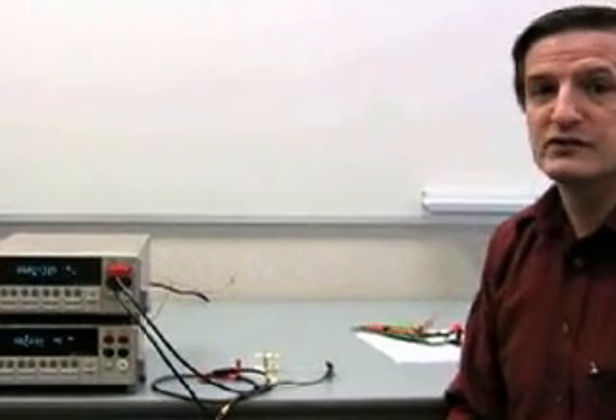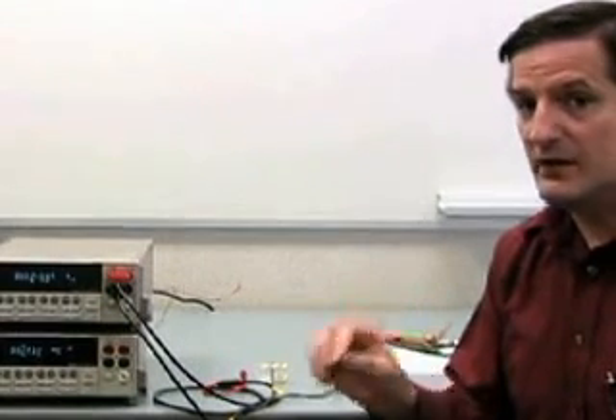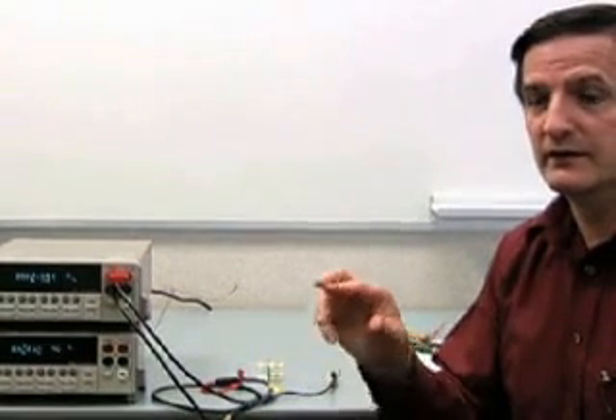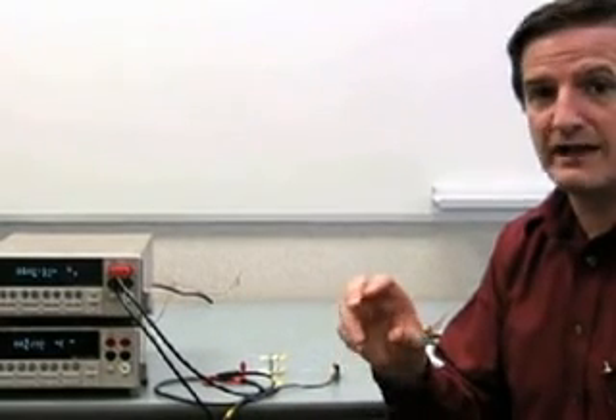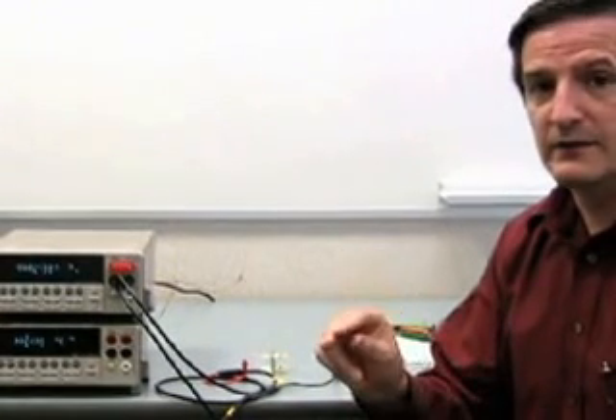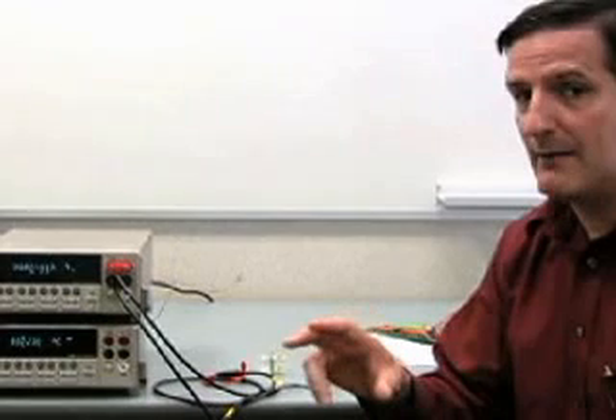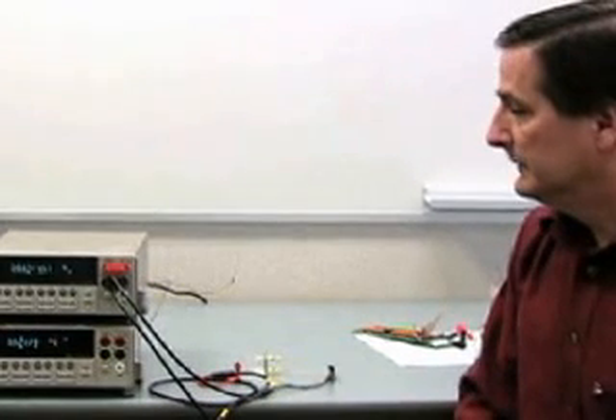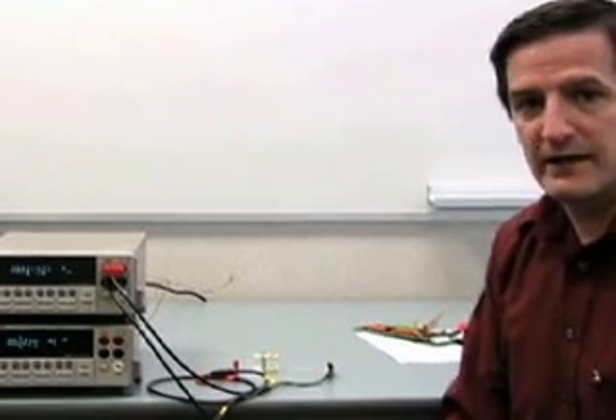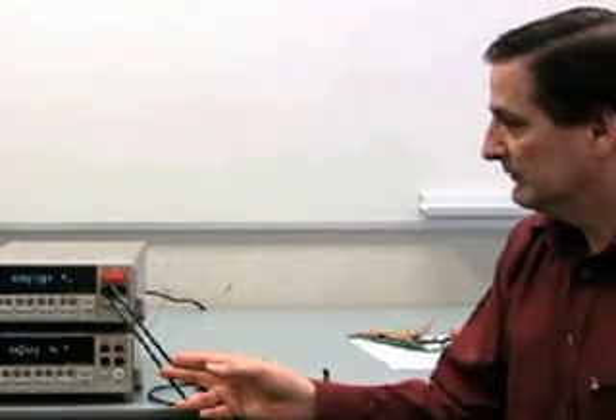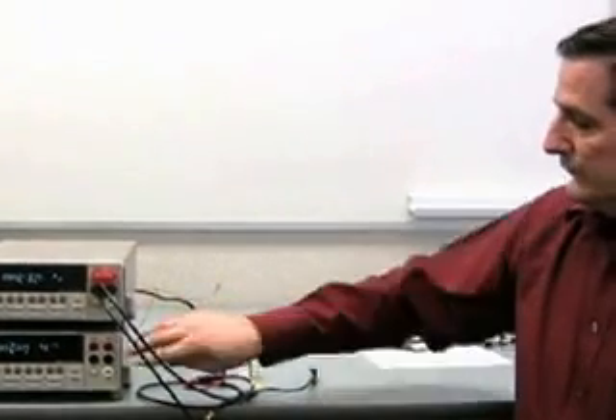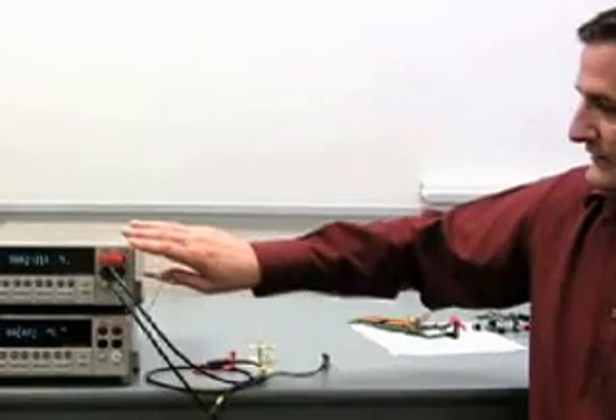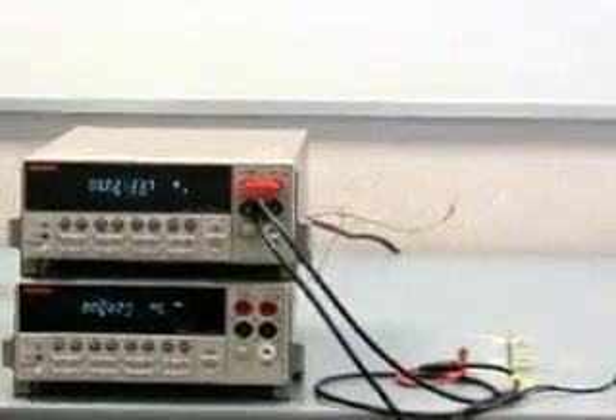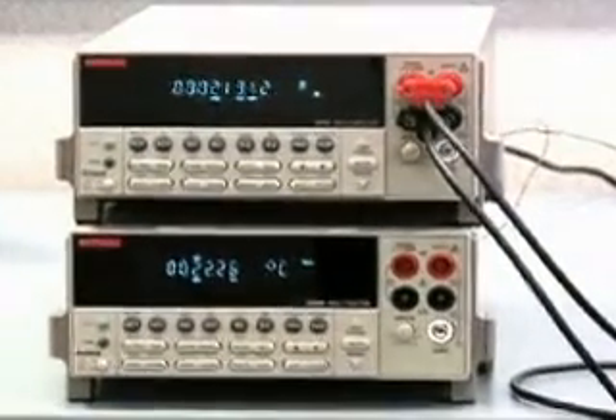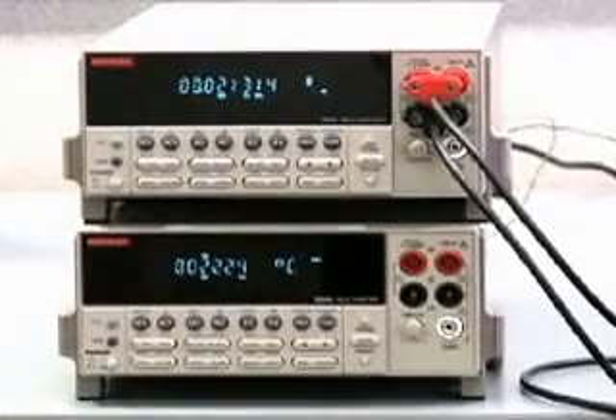It also has something called dry circuit. Dry circuit just limits the output voltage to less than 20 millivolts. 20 millivolts is a standard that says it won't puncture oxide coatings to get a less than normal resistance measurement under real applications. Those are the features of a model 2010 and the model 2000. They both have their individuals, 6.5, 7.5, and different features for each. All in all, great instruments from Keithley Instruments.